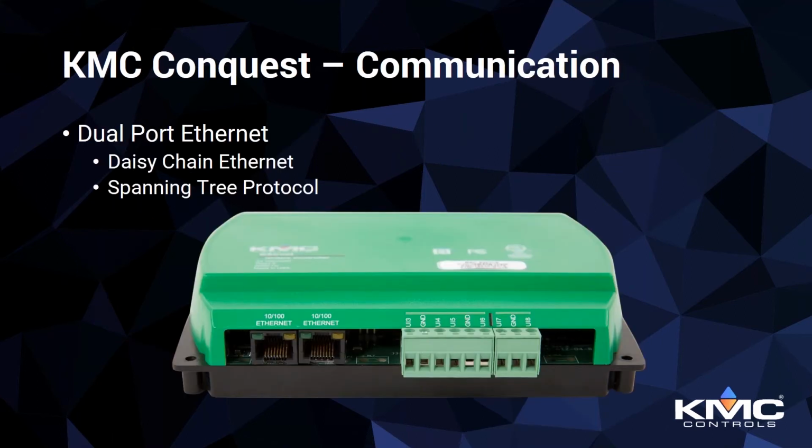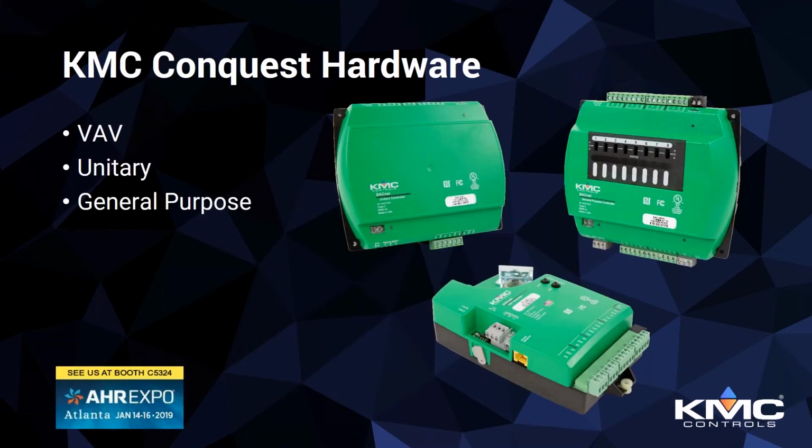Looking at our dual port Ethernet, that's one of the fun things that we have on our Ethernet models. We can actually daisy chain, so there's no need for home runs. So when you have a built-in Ethernet switch here, so you'll have two Ethernet ports, and one of them is for communicating, and then one is to switch it on to the next one. So now we're going to kind of look more at the VAV, the unitary, and the general purpose.